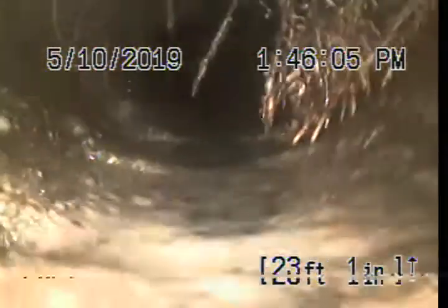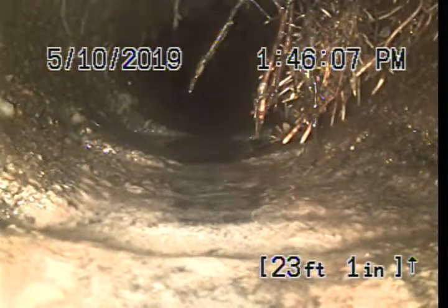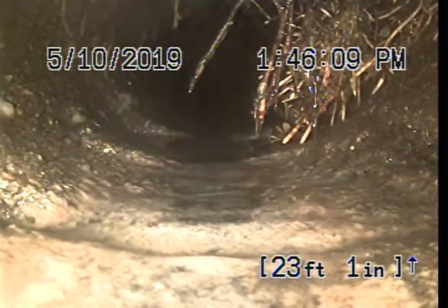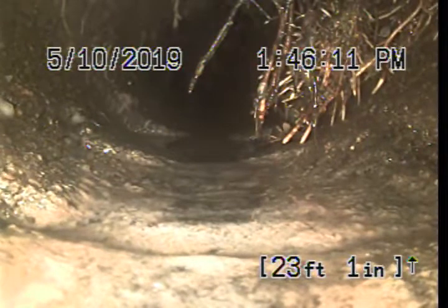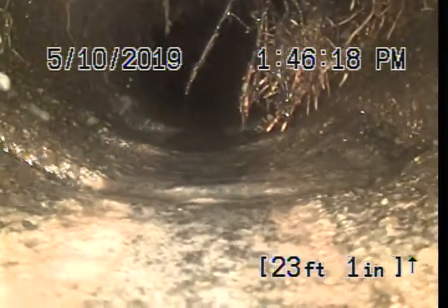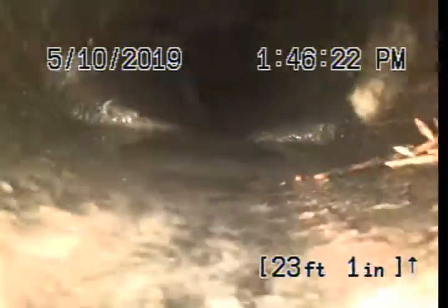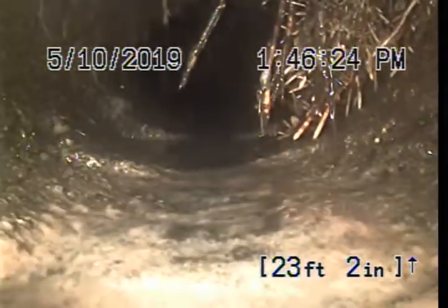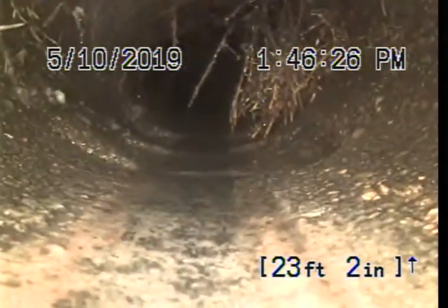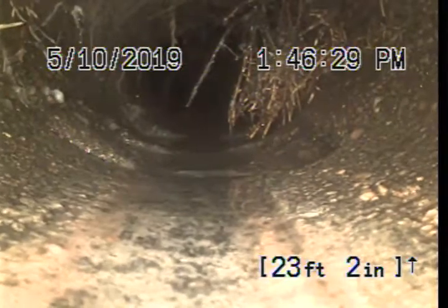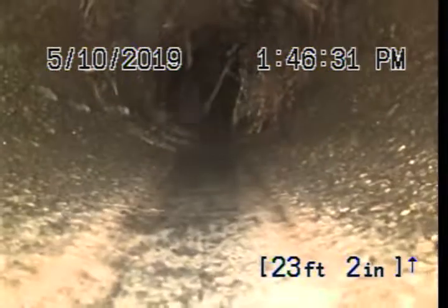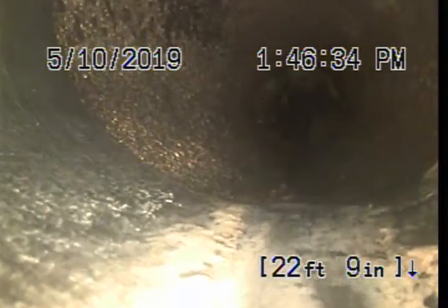Now, I do have one issue with this line here at 23 feet. What's going on is we have a little bit of a dip and a belly in the pipe. That, in addition to some of the roots coming in, makes it hard to see whether or not this line has any kind of break. It seems like there might be a break there. Having a joint area that small is not very common, but it's something that should be flushed out with a hydrojet cleaning. The hydrojet cleaning will remove all of the roots and the debris in the line, and will give us a clear picture on whether that section is broken or not.